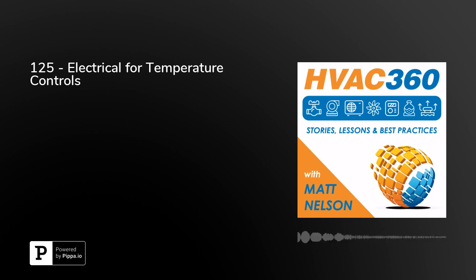Again, the 24 volts is considered low enough to be considered "safe," and I'll use that in air quotes, because really anything can be dangerous in the wrong situations. But it's high enough to really do useful work with currents that are practical. So you get that differentiation there. You don't want to be too low, but you want it to be high enough. Similar to what we were finding out with the electrical.